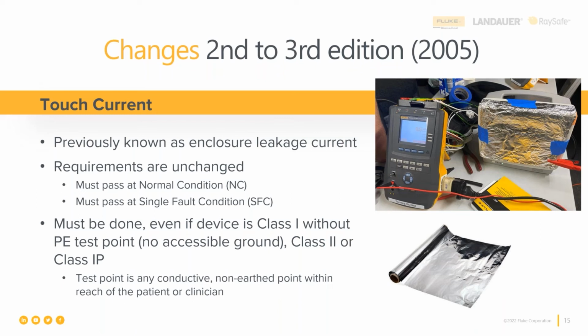Well, okay, so if we really understand that and we really do move that test lead, which by the way, an awful lot of us are not moving the test lead. Hello, you're not doing the test right if you're not moving the test lead. But today, more and more medical devices are completely covered in plastic. In fact, even some class 1 medical devices no longer have a protective earth test point for us to use.